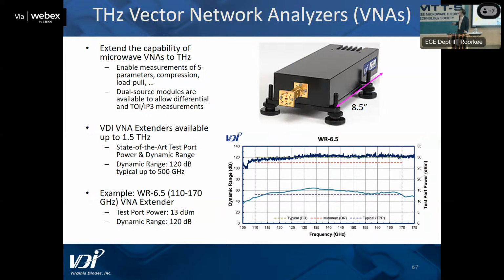So inside here are all these building blocks that I referred to before. There's two of those down converters, one for the reference and one for the received. And then there's a set of multipliers for the RF signal that comes out. This is a D-band 6.5 extender shown for an example. Dynamic range is essentially limited by the network analyzer itself, 120 dB at 10 hertz bandwidth with something like 13 to 15 dBm test port power.